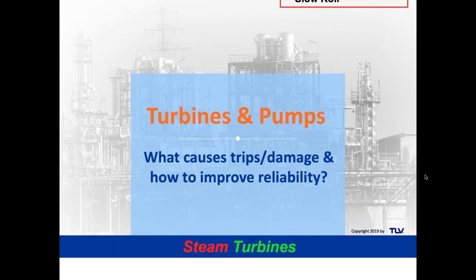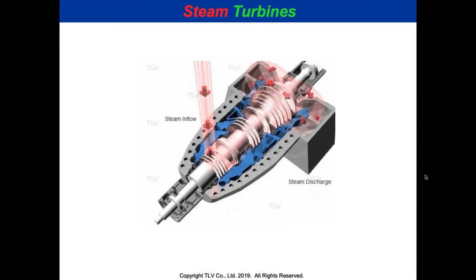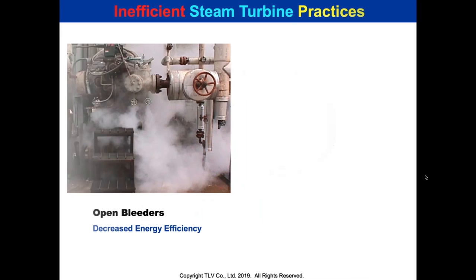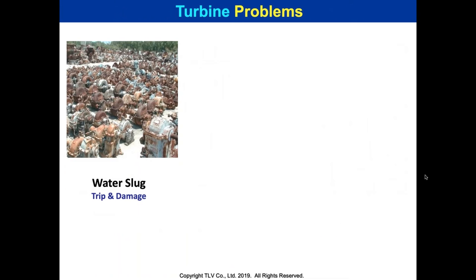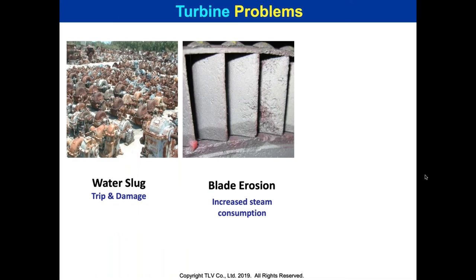Let's talk about turbines and pumps — what causes trips, damage, open bleeders, and slow rolling. Turbine blade erosion is not caused by steam — it comes from condensate carrying particles. If that condensate had been removed ahead of time through both a condensate discharge location and a separation system to disentrain moisture from wet steam, you wouldn't see that erosion.